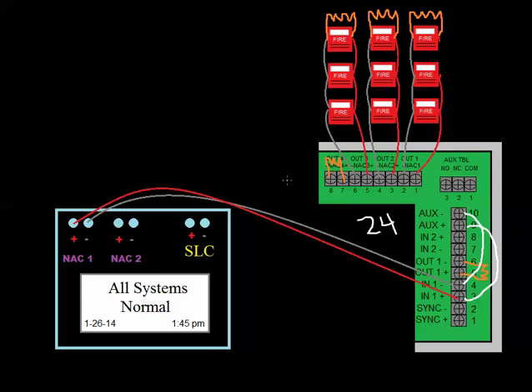If you can see any strobe, any two or more strobes that you can see from one place have to flash together. And the reason is, people with epilepsy, if you have, picture a room full of strobes that are all flashing out of sync at different times, it can cause people with epilepsy to have a seizure.